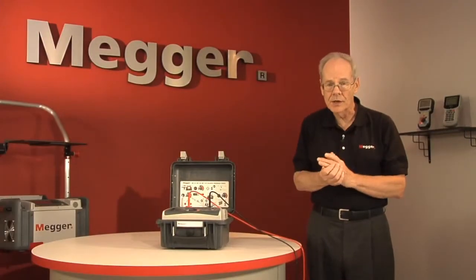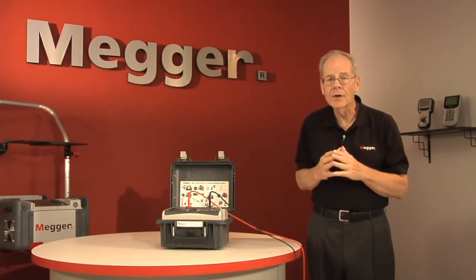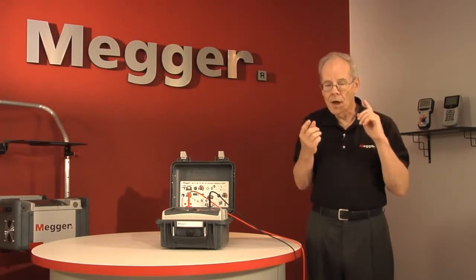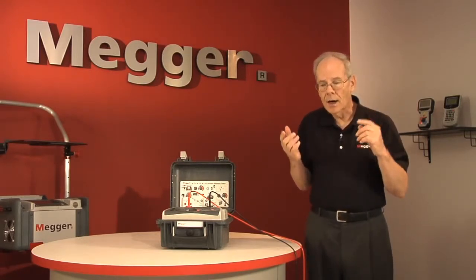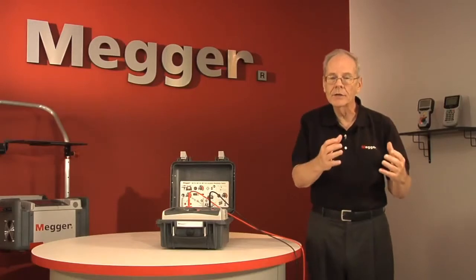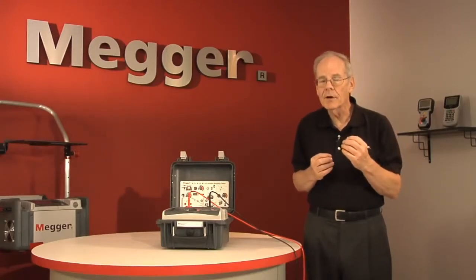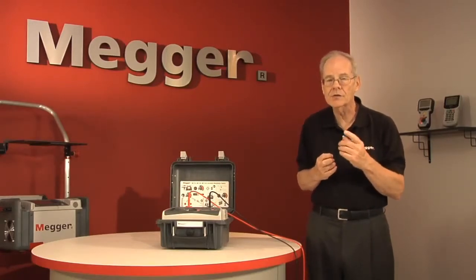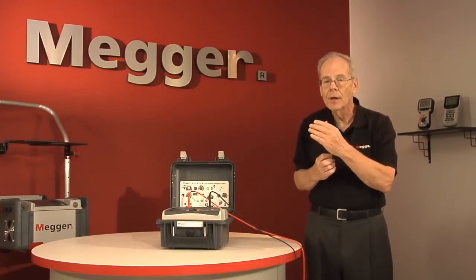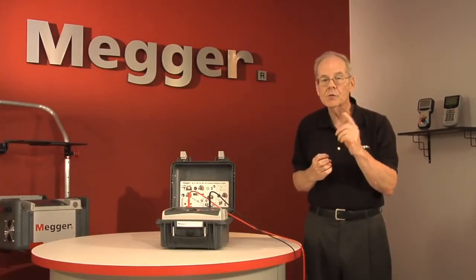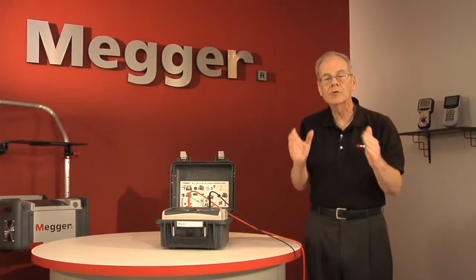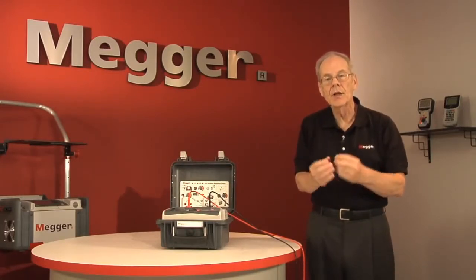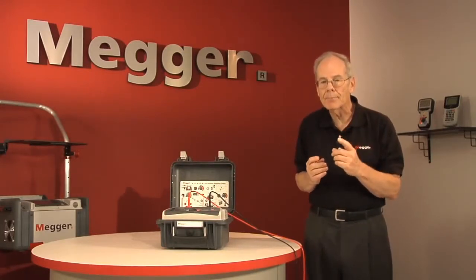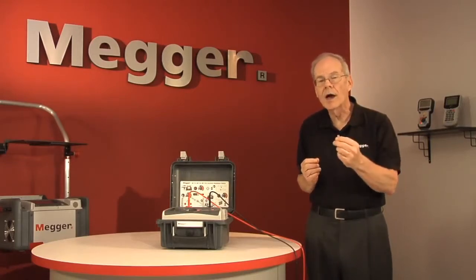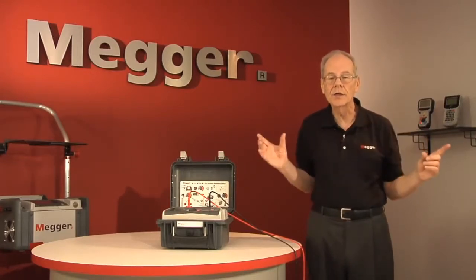The step voltage test has a particular value. It can pick up problems like brittle, dry insulation that may stand up fairly well to a spot reading test and give you a fairly good number, but the voltage increases will reveal the problems with dried and brittle insulation, and they will also spot problems like localized damage in otherwise good insulation.